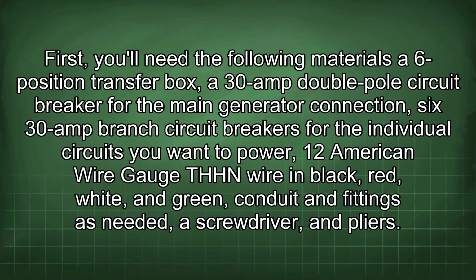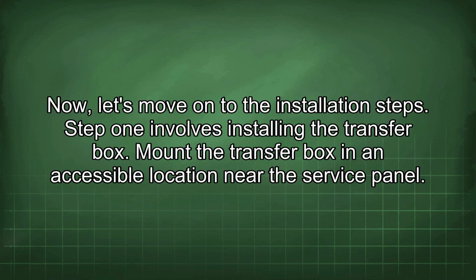First, you'll need the following materials: a 6-position transfer box, a 30-amp double-pole circuit breaker for the main generator connection, 6 30-amp branch circuit breakers for the individual circuits you want to power, 12 American wire gauge THHN wire in black, red, white, and green, conduit and fittings as needed, a screwdriver, and pliers. Now let's move on to the installation steps.